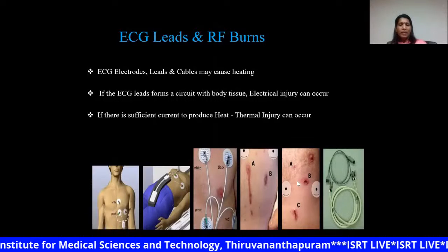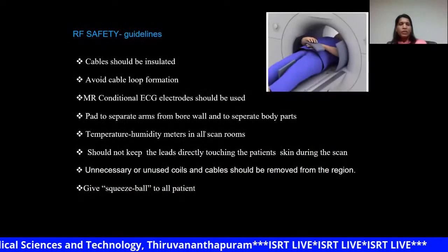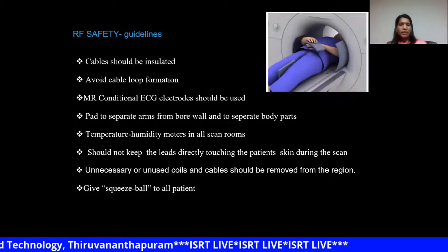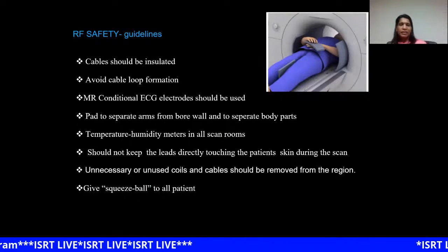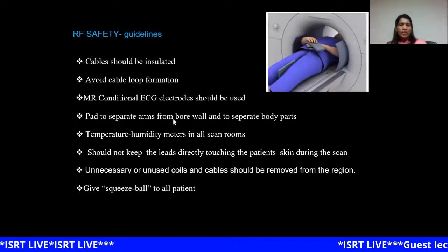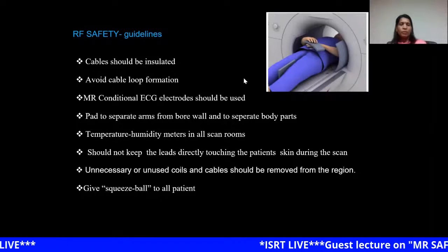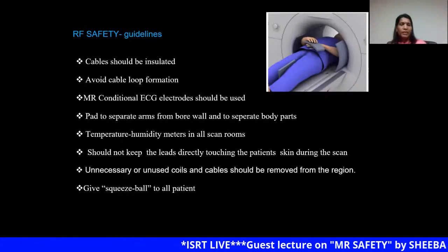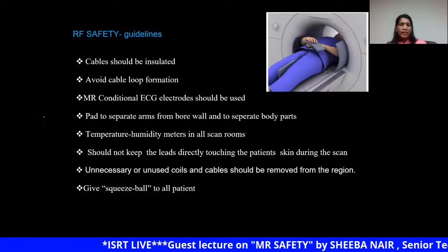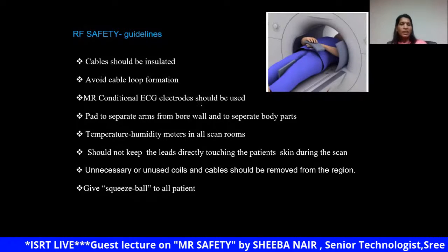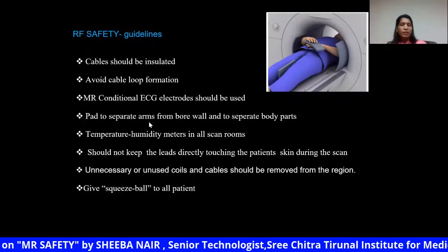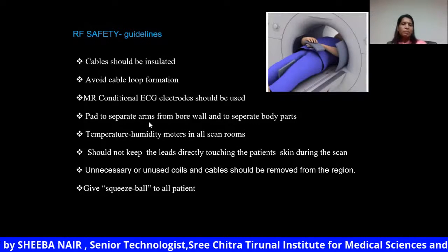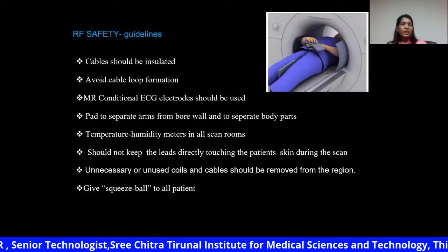So be very careful while placing these ECG leads. In order to reduce the risk of RF burns, always check whether the cables are insulated. Avoid the formation of cable loops, and always use MR conditional ECG electrodes and other monitoring devices.